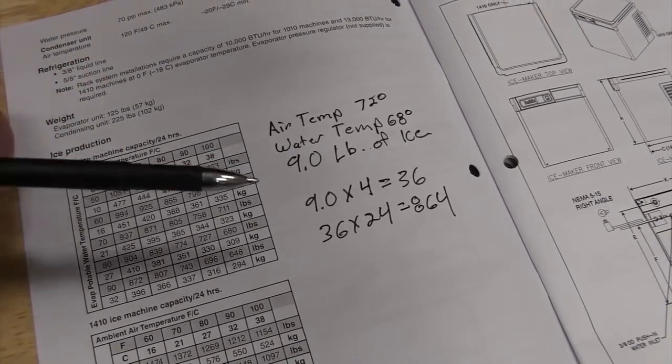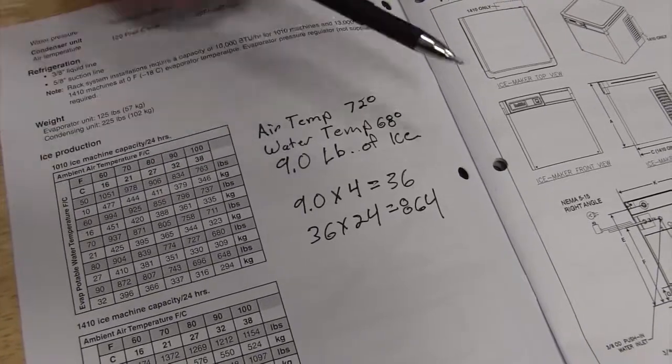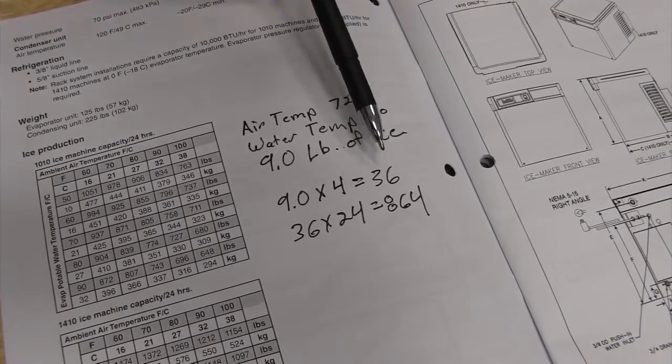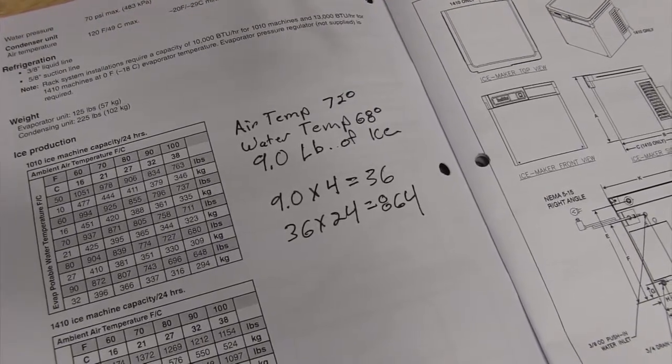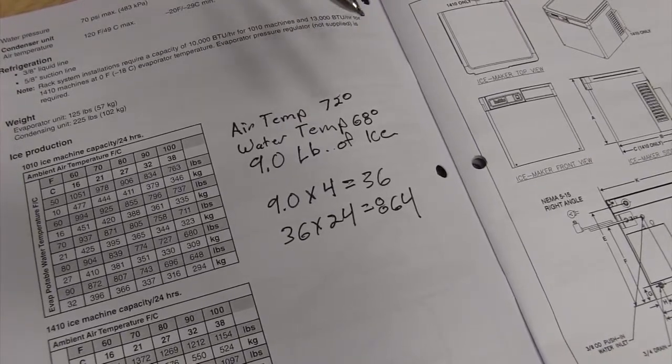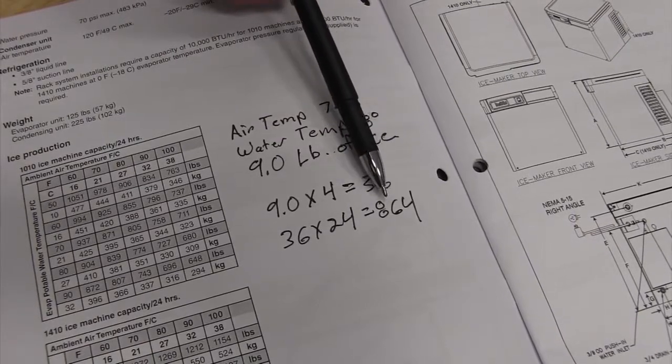So we're going to take our 9 pounds of ice and multiply that by 4. That's going to give us how many pounds per hour, which would be 36. Then we're going to take that 36 and multiply it by 24. That's going to give us how much we're making in a day. In our case, that was 864.